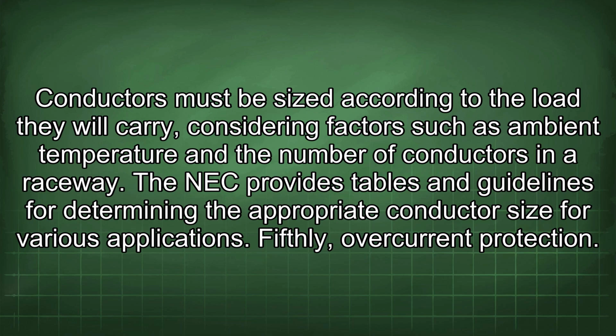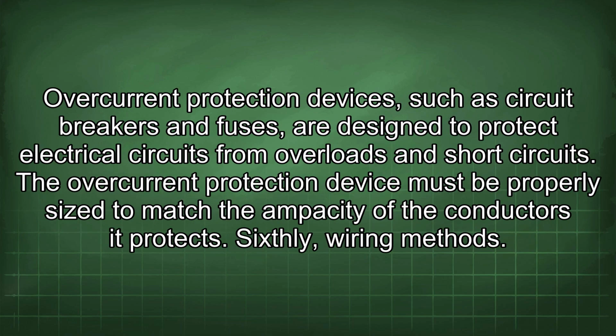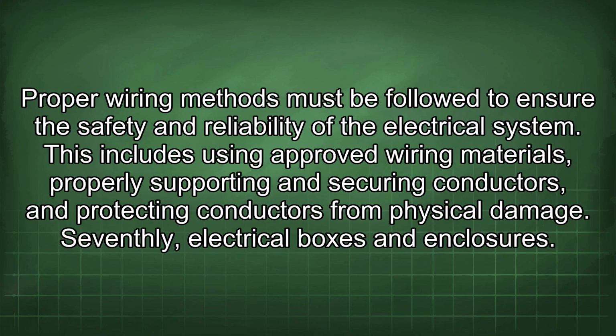Fifthly, overcurrent protection. Overcurrent protection devices, such as circuit breakers and fuses, are designed to protect electrical circuits from overloads and short circuits. The overcurrent protection device must be properly sized to match the ampacity of the conductors it protects. Sixthly, wiring methods. Proper wiring methods must be followed to ensure the safety and reliability of the electrical system. This includes using approved wiring materials, properly supporting and securing conductors, and protecting conductors from physical damage.